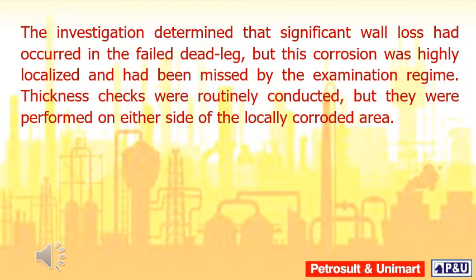The investigation determined that significant wall loss had occurred in the failed dead leg, but this corrosion was highly localized and had been missed by the examination regime. Thickness checks were routinely conducted, but they were performed on either side of the locally corroded area.